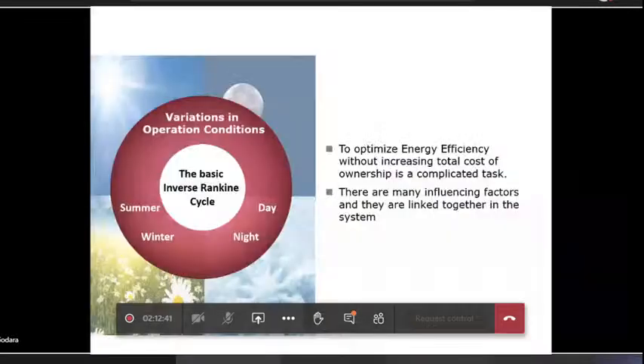So now, having looked at this situation, which is optimizing for a steady state condition, now we will look at a real life scenario. In a real life scenario, we will have variations in operating conditions. We know there is a variation of temperature in summer and in winter. We also know there's a temperature variation during the day, mornings to afternoons, late afternoons and night. And we have variations in the inside conditions. We would like a slightly lower temperature during the day. We would prefer a slightly higher temperature for cooling at night, so that we are not disturbed.